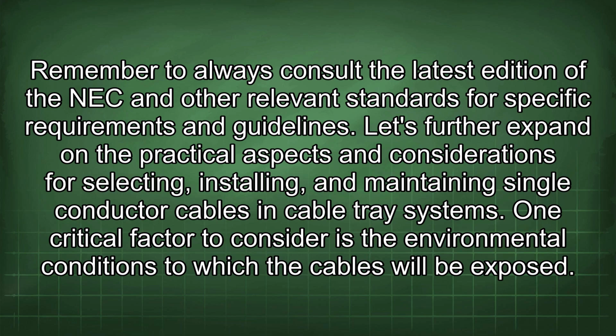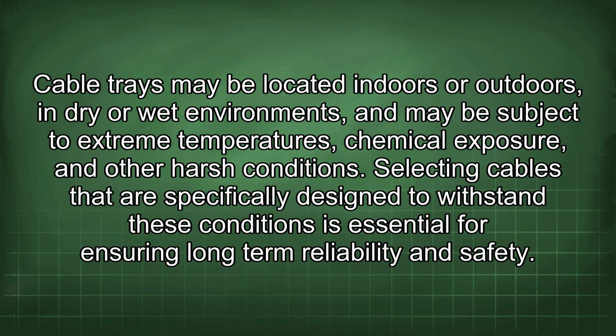Let's further expand on the practical aspects and considerations for selecting, installing, and maintaining single conductor cables in cable tray systems. One critical factor to consider is the environmental conditions to which the cables will be exposed. Cable trays may be located indoors or outdoors, in dry or wet environments, and may be subject to extreme temperatures, chemical exposure, and other harsh conditions. Selecting cables that are specifically designed to withstand these conditions is essential for ensuring long-term reliability and safety.